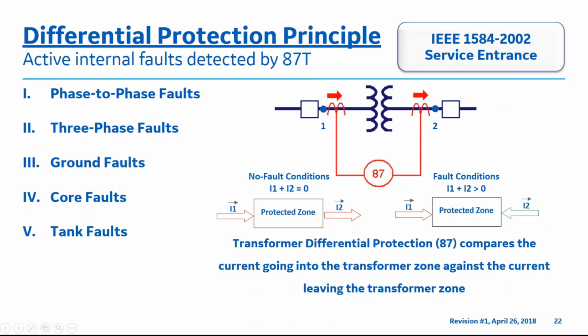In the center of this slide, under the protected zone, if I1, the current entering into the zone of the transformer, plus I2, the current leaving the transformer zone, is equal to 0, then you would have a no fault condition with this differential protection principle. On the right-hand side, there would be a fault condition if I1, the current entering the transformer, plus I2, the current leaving the transformer zone, is greater than 0. If this were to occur, the 87T would clear the fault with this method. Again, transformer differential protection, 87, compares the current going into the transformer zone against the current leaving the transformer zone.